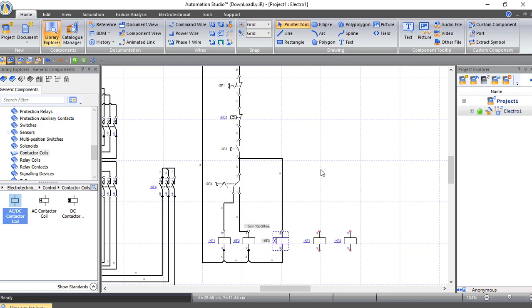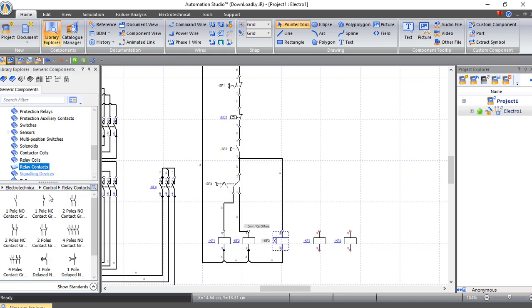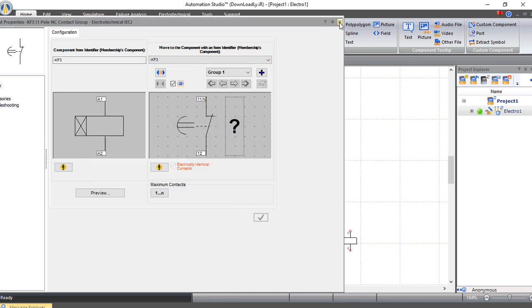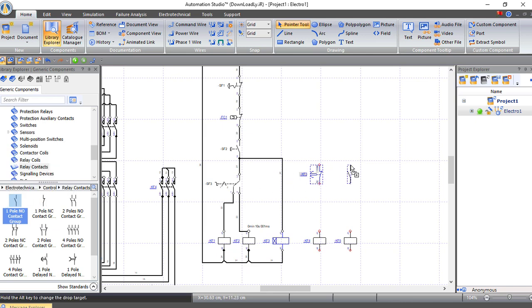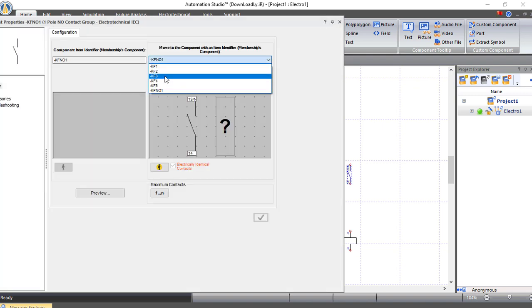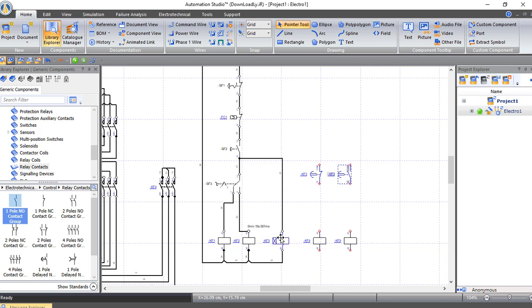Now I will bring two auxiliary contacts from the timer to make those contactors work and stop. From Relay Contacts I will choose a normally closed contact and connect it to timer KF3. I will bring another one which is normally open and also connect it to KF3. At the beginning the timer will count up to 10 seconds — before 10 seconds this one is normally closed and this one is normally open. After 10 seconds this will open and this will close, switching from star to delta.